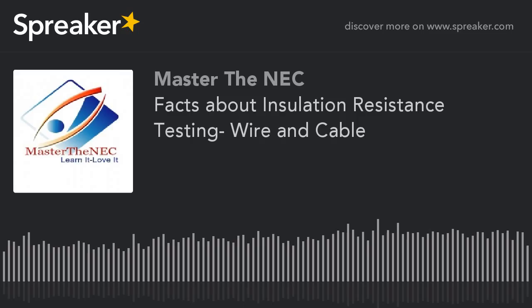All right, so you have to understand what the testing is there to do. Take two insulated conductors, whether it's tray cable, MC cable, or individual conductors pulled in a PVC raceway. When you're measuring insulated conductor to insulated conductor, you're only looking for total damage. You're looking for something that continuity wouldn't pick up because maybe it's damaged, but not all the way down to the conductive material. Yet the insulation is damaged, so it's just a quick test.